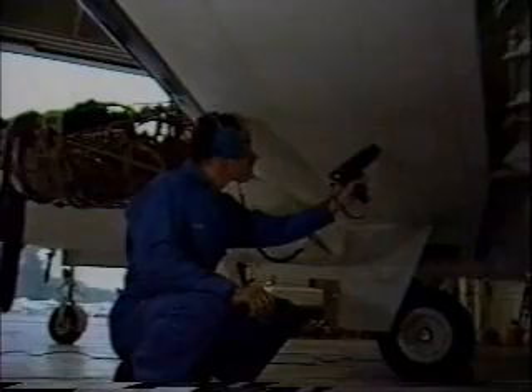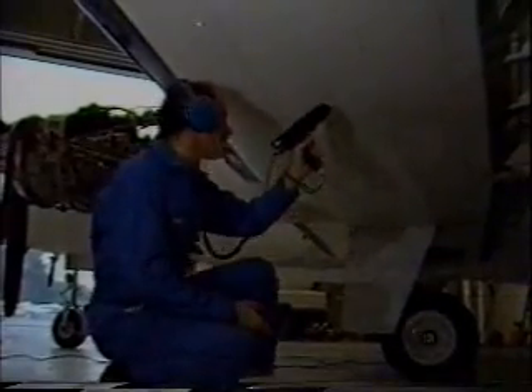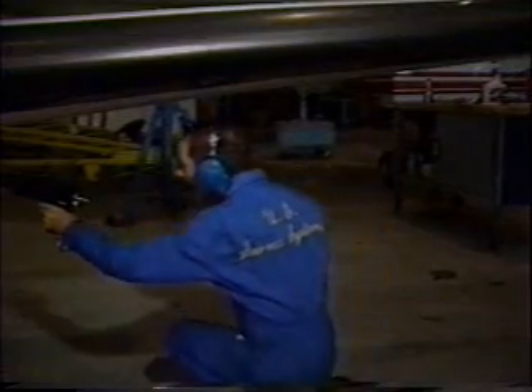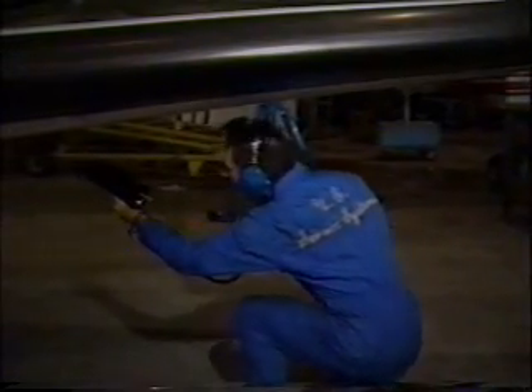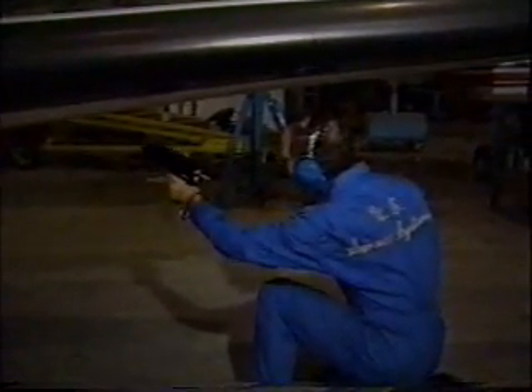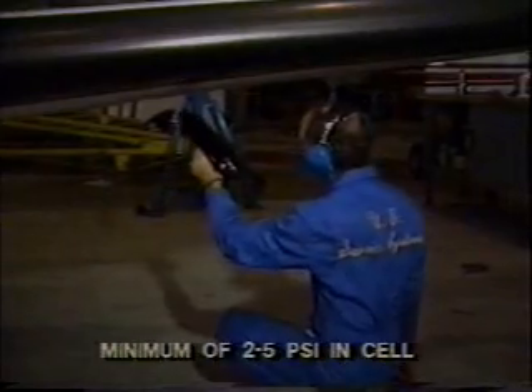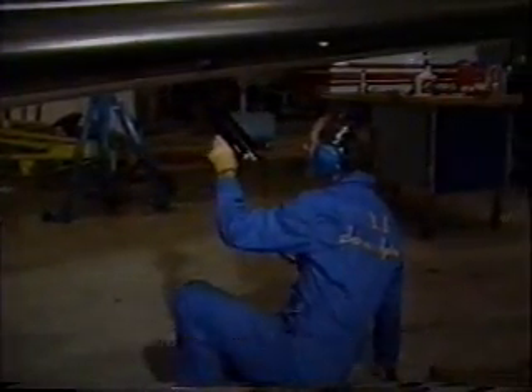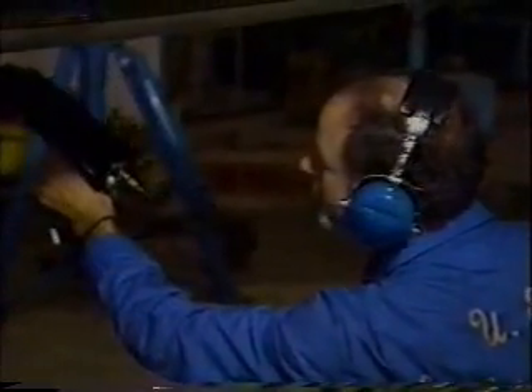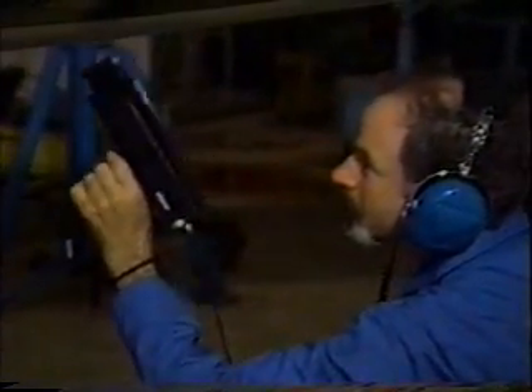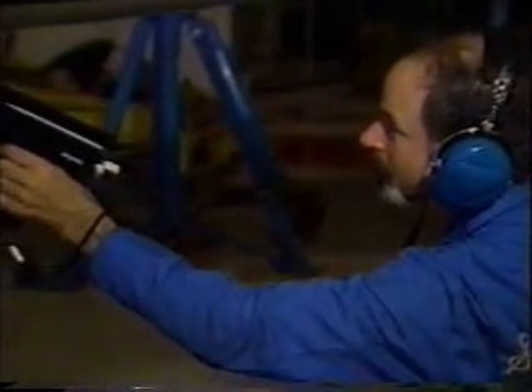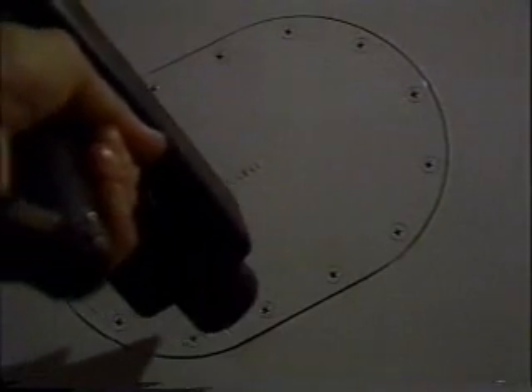Next, we'll show you how to use the ultraprobe to inspect fuel cells. To check a wet fuel cell for leakage, the tank is drained and pressurized with air or nitrogen. There must be a minimum of 2 to 5 psi within the cell for the test to be accurate. We then scan following the rushing sound. In certain cases, you may hear a crackling sound from residual fuel in the tank as it is forced through the leak hole.